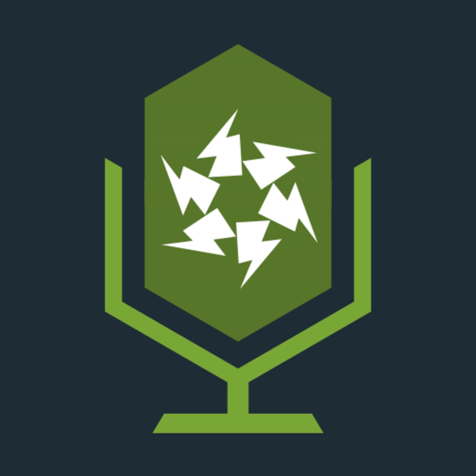In zone 0, current using equipment shall only be installed provided the following requirements are met. The equipment complies with relevant standards. It's fixed and permanently connected, so not on a plug and socket or anything. And is supplied by a voltage of SELV, which is again the safest protective measure that we have. Electrically isolated, extra low voltage. Not very practical when we're doing a lot of work, but in the bathroom it's okay. But they've restricted the voltage even further. So it's SELV, but to 12 volts. So it's a lowered version of SELV.